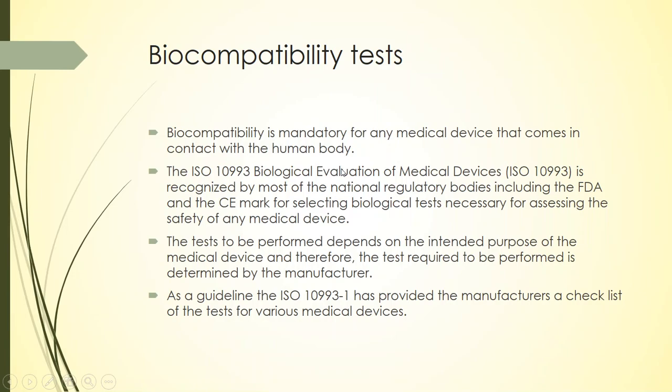So there's a standard directive called ISO 10993, which is the Biological Evaluation of Medical Devices directive, and it is one of the most recognized guidelines by national regulatory bodies, including the FDA and the CE mark. And this guideline actually gives the manufacturer an insight into the biological tests that are necessary for assessing the safety of any medical device, right? The tests should be performed depending upon the intended purpose of the medical device.